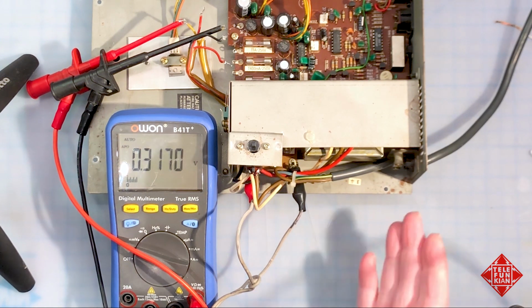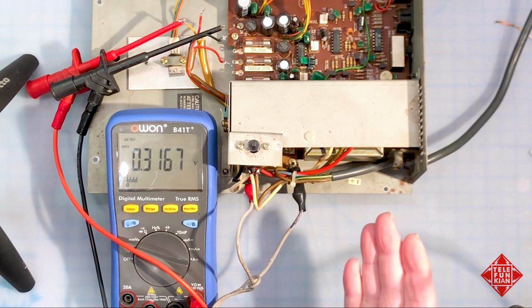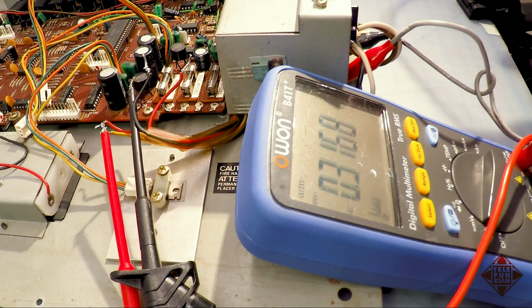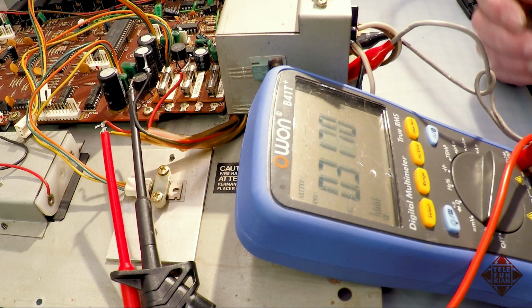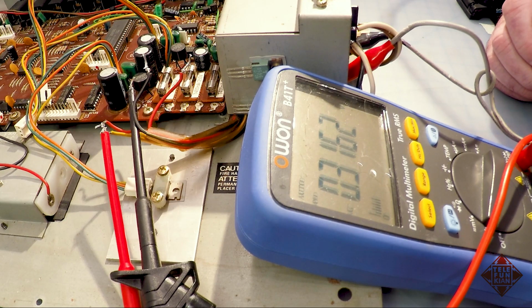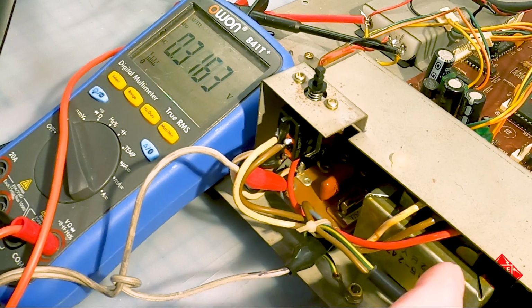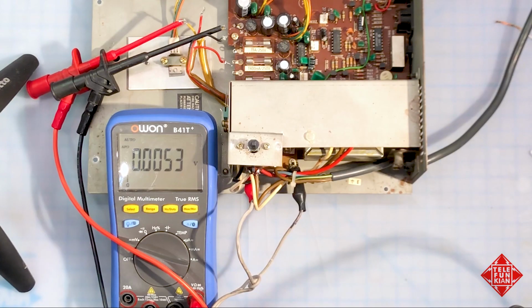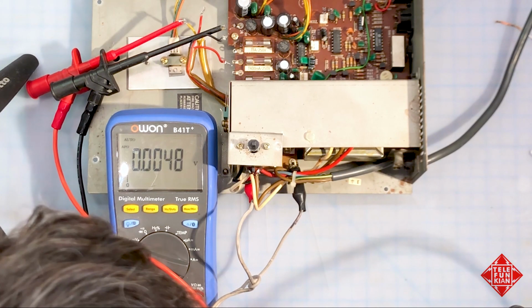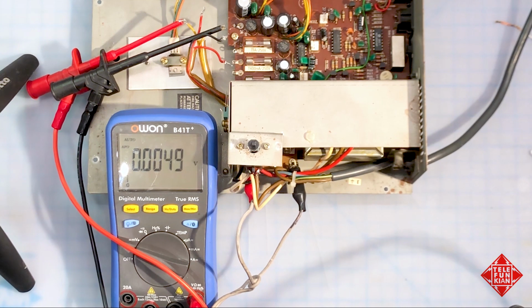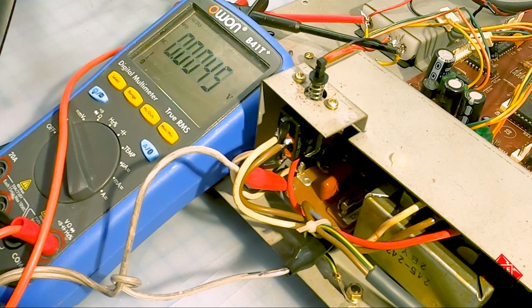So really there's nothing else other than the switch and the fuse between the transformer and our reading here, so this transformer is damaged somehow - damaged in such a way that the winding deriving the 5 volts isn't giving us enough voltage for the supply.